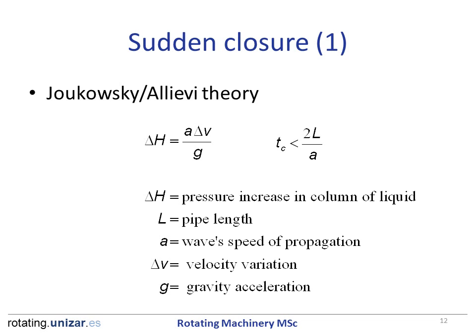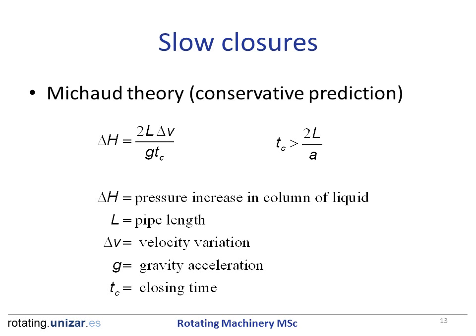For sudden closures, the pressure variation is estimated according to the Joukowsky-Alievi theory. In that case, the variation in pressure expressed in column of liquid equals the celerity times the velocity variation divided by the gravitational acceleration. In slow closures, Michaud's theory estimates that the pressure variation expressed in column of liquid equals twice the length of the pipe times the variation of the velocity, divided by the acceleration of gravity and the closing time.